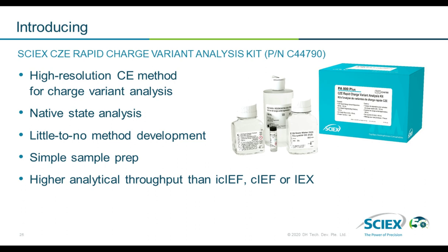And the sample prep is non-existent. It's just dilution in water. That's as easy as size exclusion chromatography. Right? The method development is already done for you. The separation buffer itself coats the bare fused silica capillary, which really just makes the method a breeze. The bare fused silica capillary is maintenance free. The sample buffer that we're using is just water.